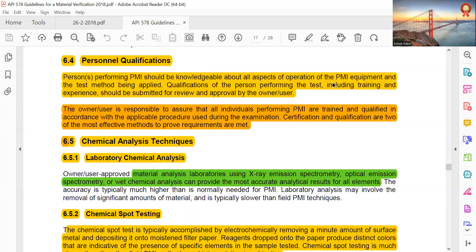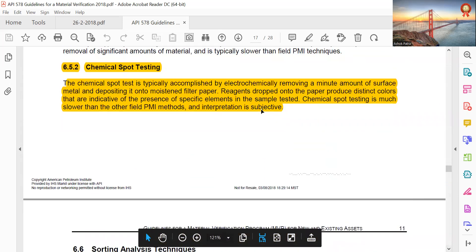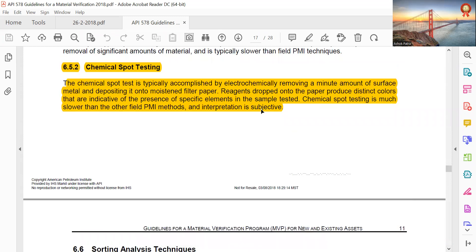Certification and qualification are two of the most effective methods to prove requirements are met. Chemical Analysis Technique: material analysis laboratories using X-ray emission spectrometry, optical emission spectrometry, or wet chemical analysis can provide the most accurate analytical results for all metal elements. Chemical spot testing is typically accomplished by electrochemically removing a minute amount of surface metal and depositing it onto moist filter paper. A reagent dropped onto the paper produces distinct colors indicating the presence of specific elements. Chemical spot testing is much slower than other PMI methods and interpretation is subjective.